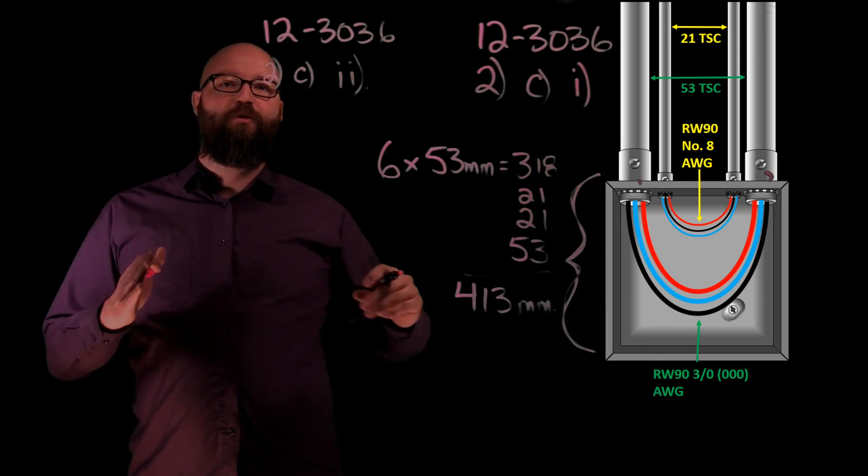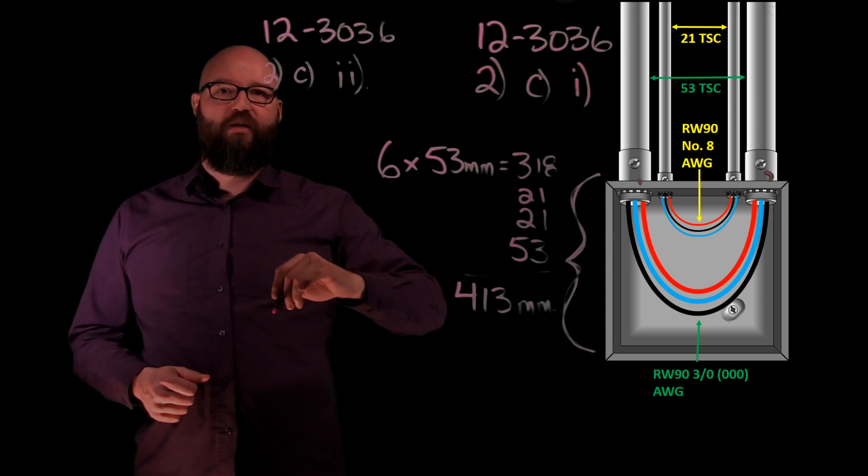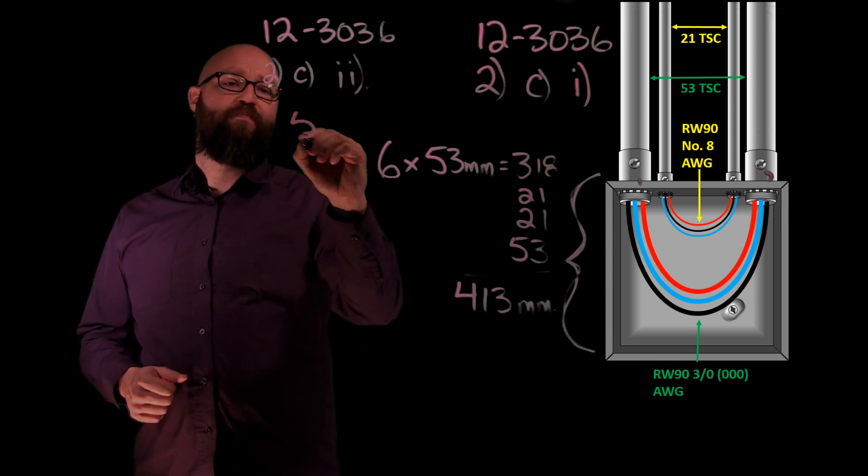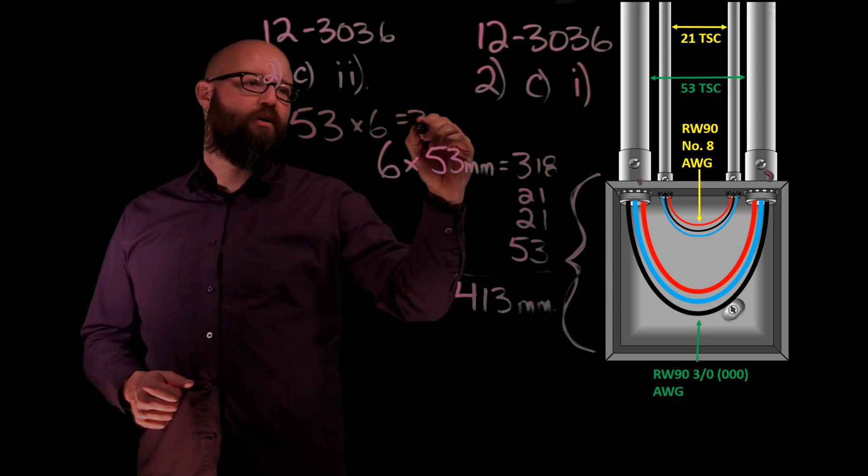I'm going to make sure that the distance between the inside, the innermost point of those conduits, is at least six times the largest trade size. So in that case we have 53 times six, again equals that's 318 millimeters.